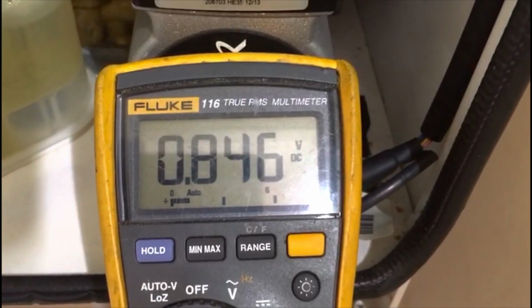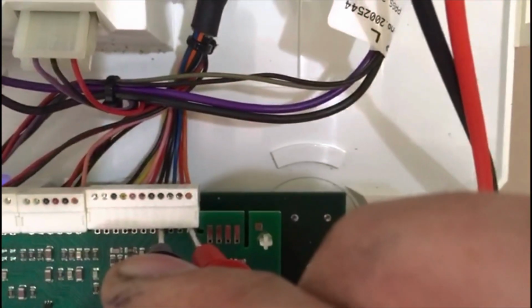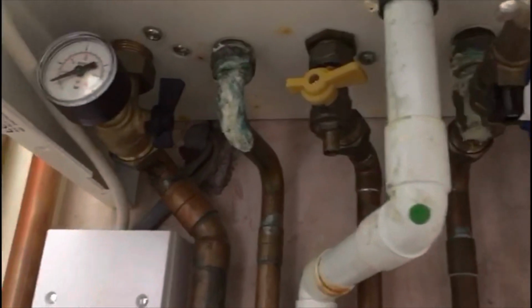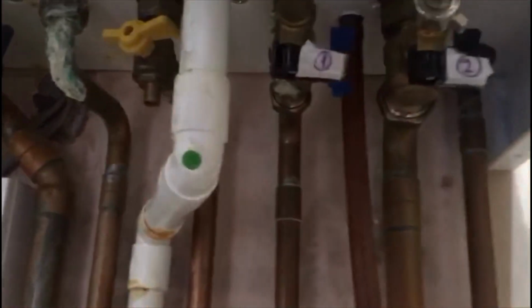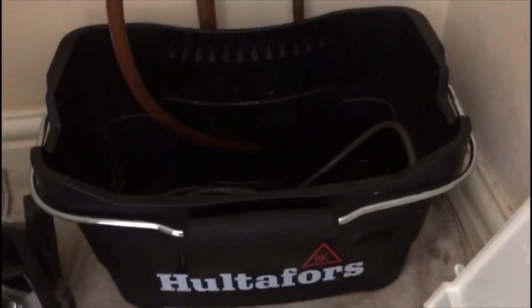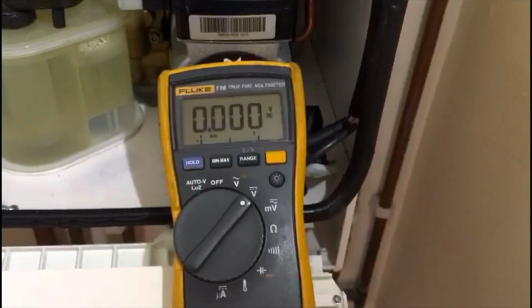So what I'm going to show you now is what happens when you drain the boiler. I'm going to drain the boiler and have my multimeter connected, and as I'm draining it, you'll see the signal from the transducer to the circuit board changing. You'll see the voltage dropping, and that's just to show you how it works. So that's what I'm doing now. I've got it drained into a bucket. The boiler's draining down slowly, and if you can see the multimeter, you can see the voltage dropping, and that's just showing you that the transducer's working properly.